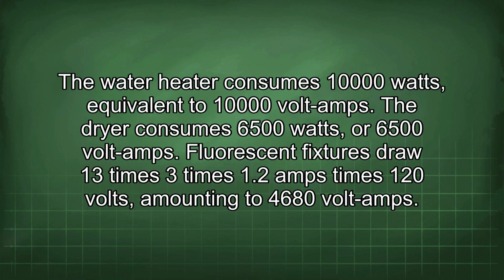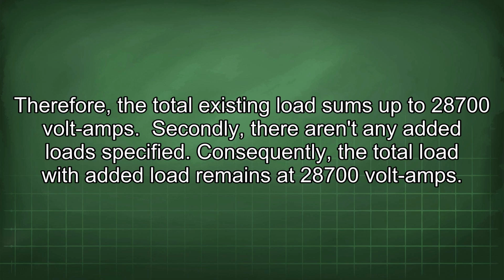The water heater consumes 10,000 watts, equivalent to 10,000 volt amps. The dryer consumes 6,500 watts, or 6,500 volt amps. Fluorescent fixtures draw 13 times 3 times 1.2 amps times 120 volts, amounting to 4,680 volt amps.